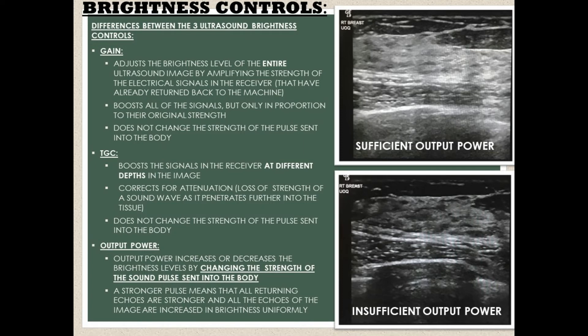Output power increases or decreases the brightness levels by changing the strength of the sound pulse sent into the body. And just like gain, it changes the brightness of the entire image. A stronger pulse sent into the body means that all returning echoes are stronger, and all the echoes of the image are going to be increased in brightness uniformly.